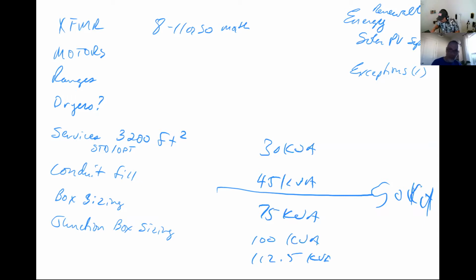So that's all I know about transformers, except for one last quick note. I don't see it very often, but on page 337 there are some ventilation requirements for transformers, listed in 450.45(C) on the right-hand side of the page. In case you run across it, the minimum size opening for ventilation for a transformer is based off of the kVA, so it's a square inch per kVA of transformer capacity in service.